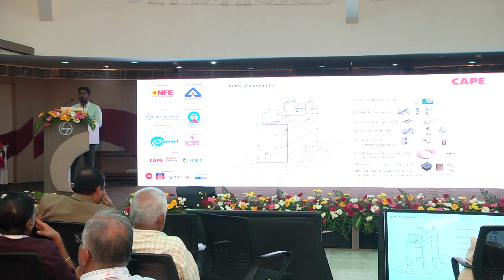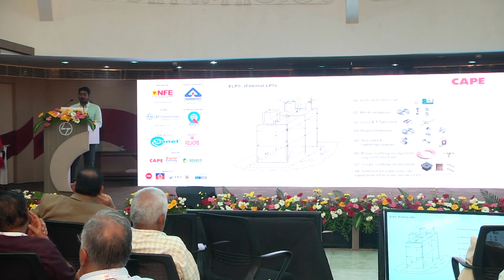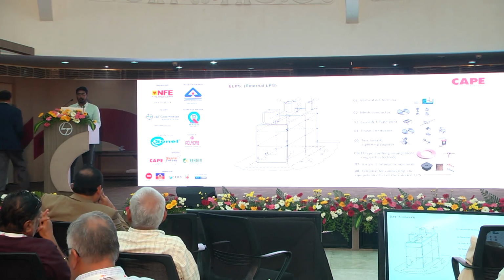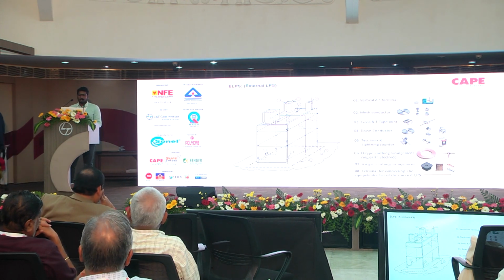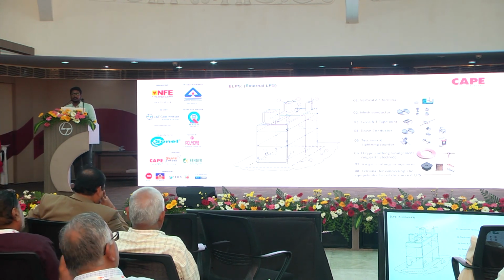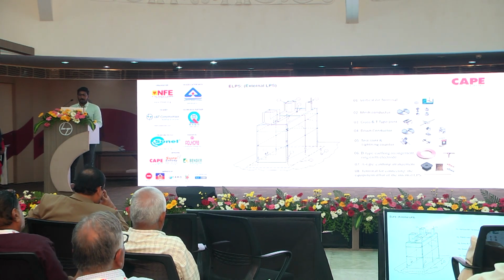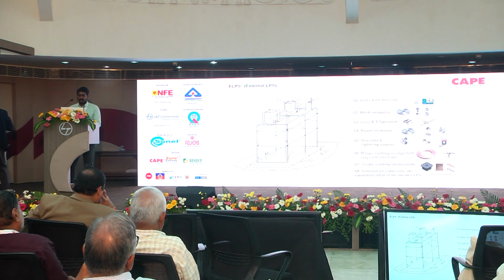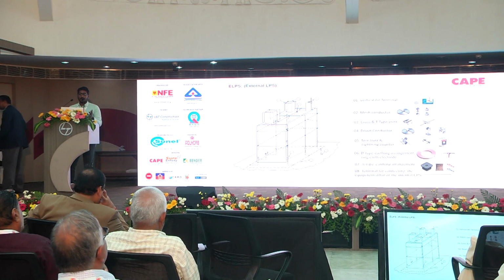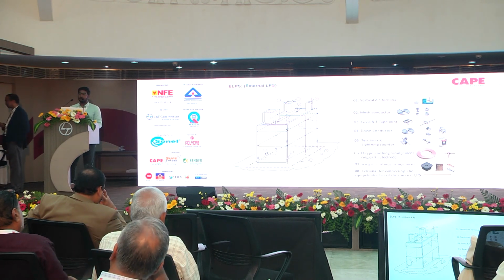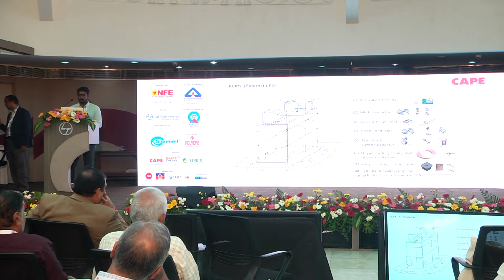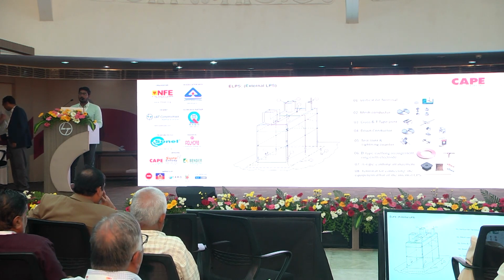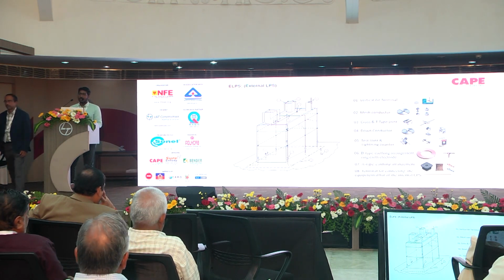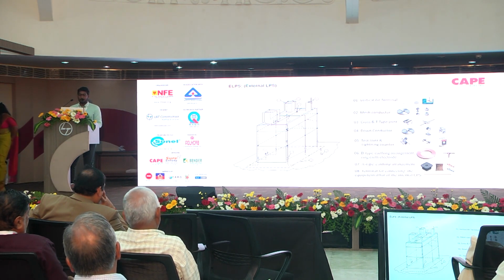As we know, aluminum conductors tend to contract and expand during temperature variation. So in order to avoid that, expansion pieces will be provided at equal intervals. And next are the cross and T-type joint connections, which are SS accessories. And for the down connector, the same type of 8 mm aluminum conductor is recommended with suitable accessories. In the air termination part, as we said, in order to maintain equipotential bonding, the metallic structure parts need to be bonded with the LPS system. For that, suitable accessories like a folding clamp or any additional cable clamps will be used.